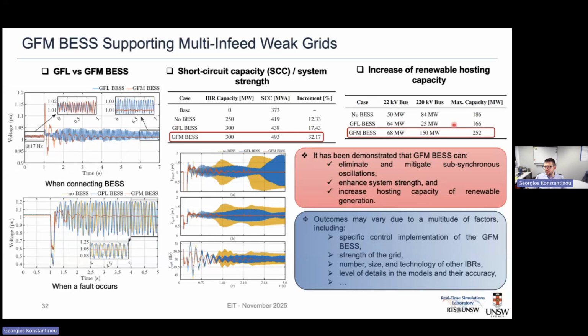As an extra benefit, if we explore adding more and more inverter-based resources in that particular location, we can see that in the case of a grid-forming battery, we are able to add extra. So we have the option, not that we would like to do it in these particular conditions, of increasing the amount of renewables we can add, or inverter-based resources, not only renewables, in the lower voltage bus, so the medium voltage 22 kilovolt bus, or in the higher voltage 220 kilovolt bus. So you can see that this takes us to a capacity of 252 megawatts that we can accommodate in that particular area without any stability issues.